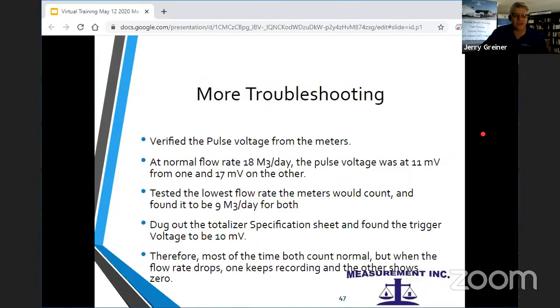So then we did some more troubleshooting. We verified the pulse output voltage from the meter. So right on the magnetic pickup probe, you can read that output voltage. On this one, normal flow rate 18 cubes a day. They had different voltages coming out of them. One was 11 millivolts, the other was 17 millivolts. We tested them both and found that they would count down to the 9 cubic meters per day for both.